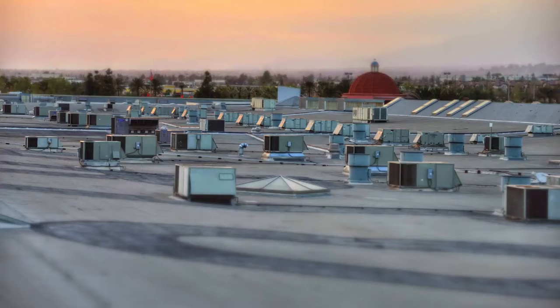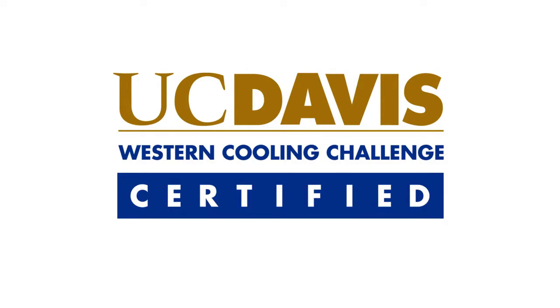We have also focused a lot of our research, though it's not seemingly so sexy or interesting as the design of very elegant new building systems, on advances for rooftop packaged air conditioners. That's to recognize that 80% of the individual pieces of equipment that do heating and cooling in the United States, at least, are rooftop packaged air conditioners. Something like 65% of the total commercial floor area is cooled and heated by rooftop packaged air conditioners. So if we're going to make a difference in all of the existing buildings in order to drive down our energy use and carbon emissions, we really need technologies that can address this market.